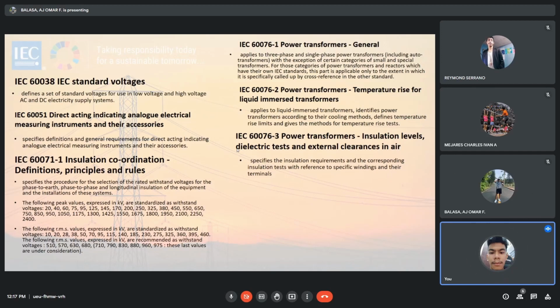Dito sa IEC 60076-2, Power Transformers Temperature Rise. So, nabanggit natin kanina yun sa temperature rise doon sa may general standard doon sa unang-unang part ng 60076-1. Sabi dito is, karagdagan na pala to. So, it is assumed throughout this part that the service temperatures of different parts of a transformer can each be described as the sum of the external cooling medium temperature, ambient air or cooling water, and the temperature rise of the transformer part. Normal temperature rise limits applies unless other service conditions are specified.